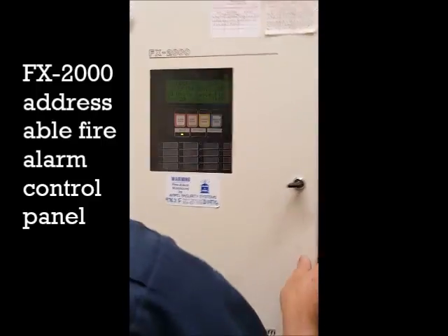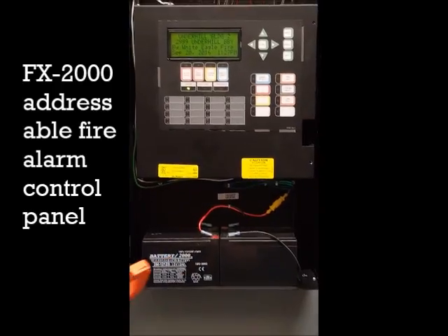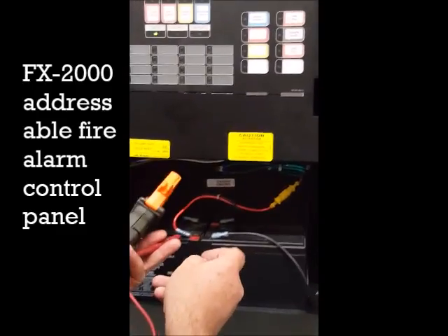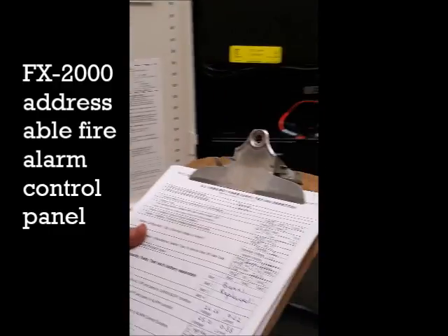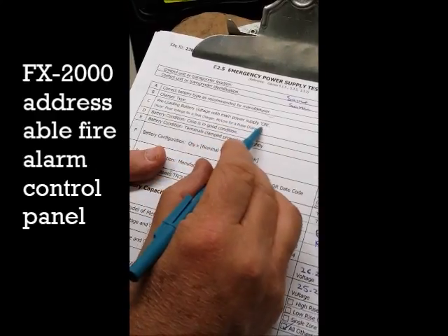This is FX2000 Mircom, and this panel is an addressable panel. Like the other panel, we have to start with battery test. We put the meter on voltage DC and measure the voltage when the AC is on. If you look at the paperwork, we have pre-loading battery voltage with main power supply on.